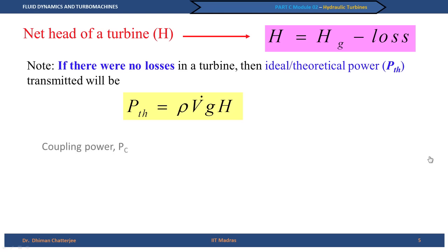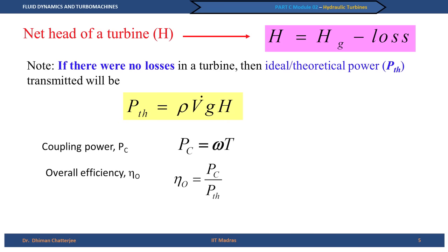Accounting for these different losses, what we ultimately get from the turbine is the coupling power P_C, given by ω times T (rotational speed times torque). The ratio of P_C to the theoretical power is called the overall efficiency. The key concept to keep in mind is the ideal power, the actual power, and the efficiency.